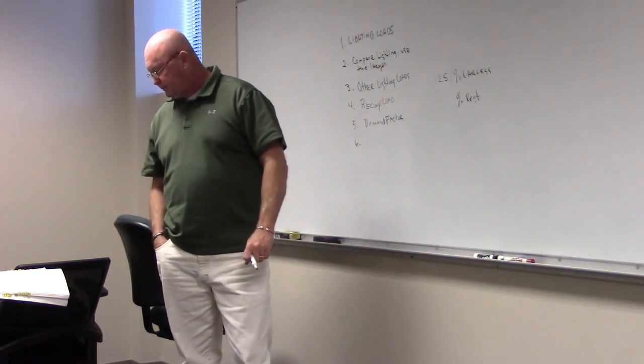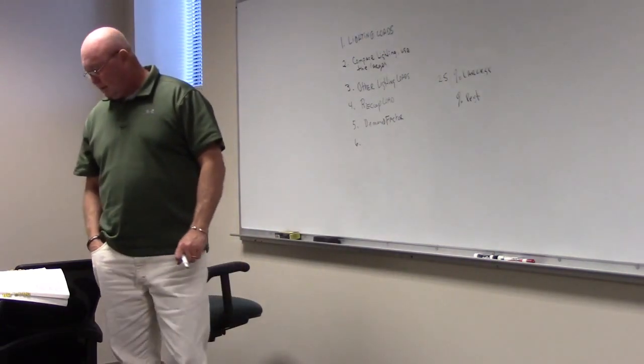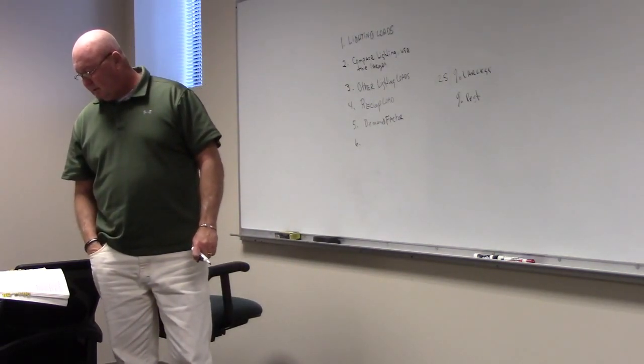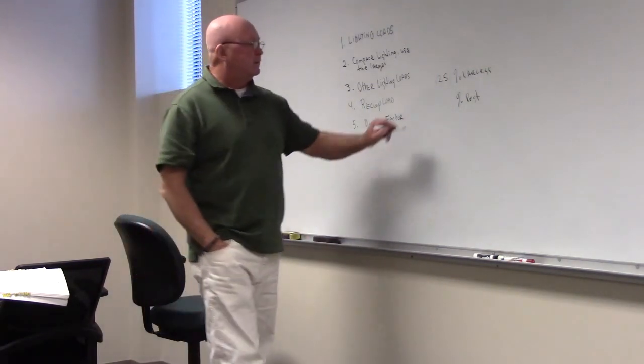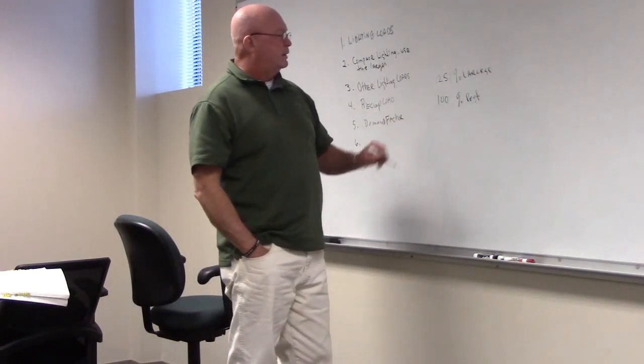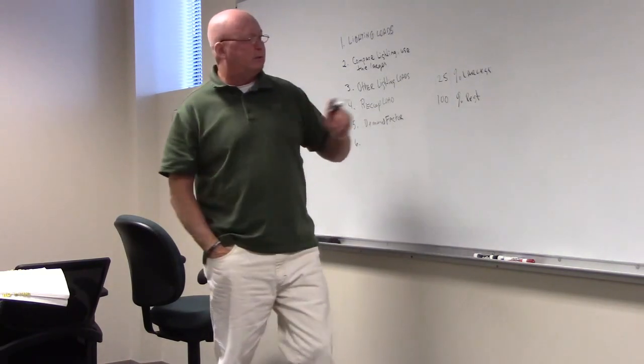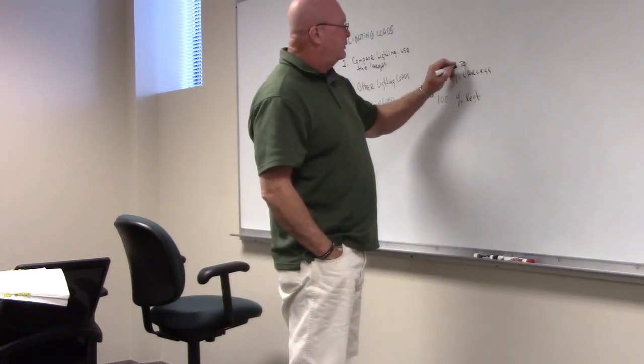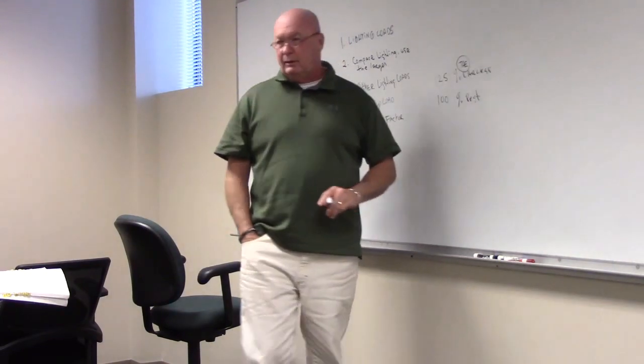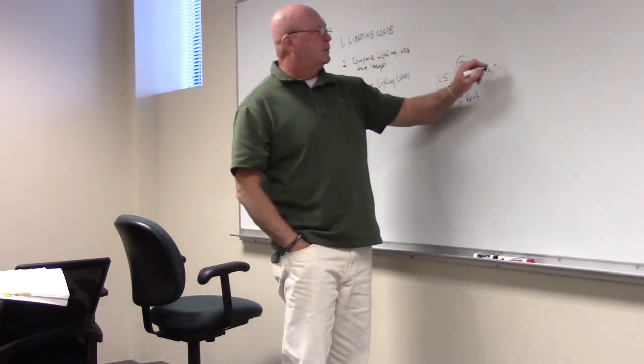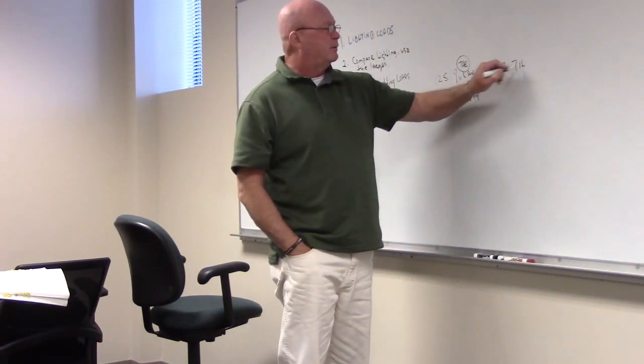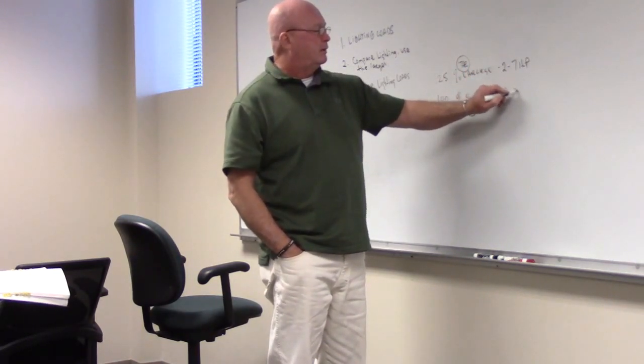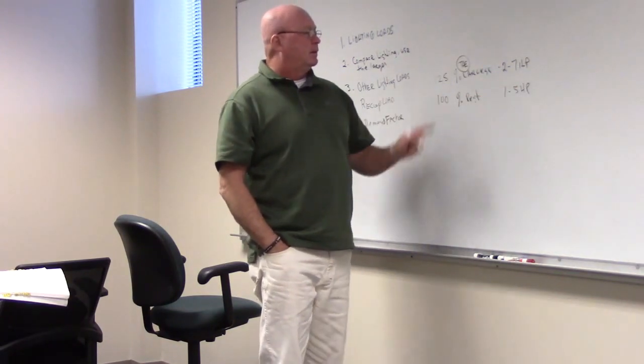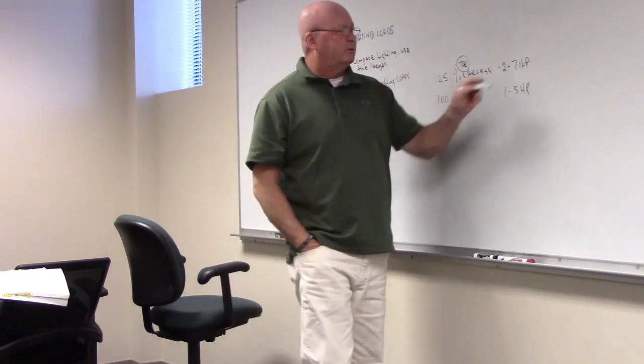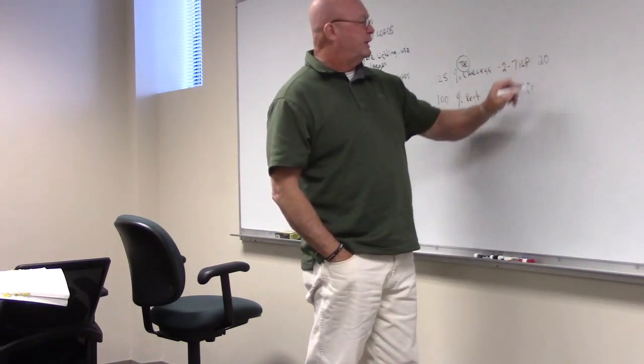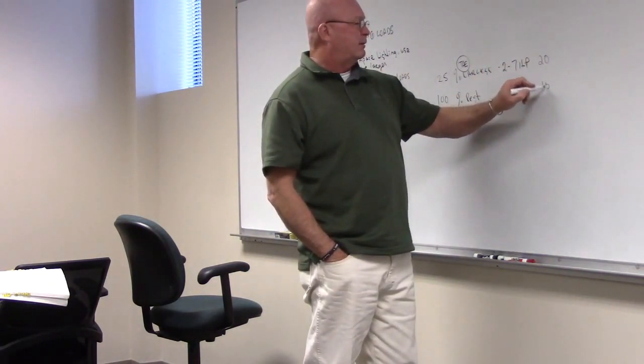What does it say there? In your book, step 6. 100%. Okay, 100% for the rest, and that's the key too, the largest motor gets the 125%. You may have two 7 horsepower, one 5 horsepower. Let's just throw a number out there. Let's say these are 20 amps, and let's say these are 15 amps.